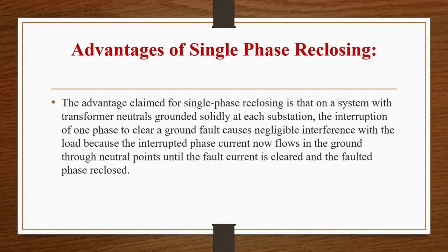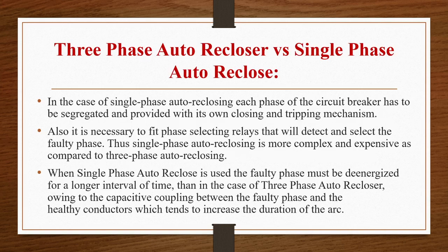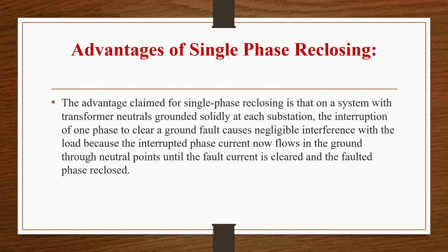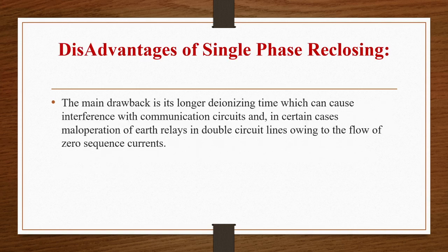We are now going to see the advantages of single phase reclosing. The advantage which is claimed for single phase reclosing is that, on a system with transformer neutrals grounded solidly at each substation, interruption of one phase to clear a ground fault will cause negligible interference with the load, because the interrupted phase current now flows in the ground through neutral points until the fault current is cleared and the faulted phase is reclosed.